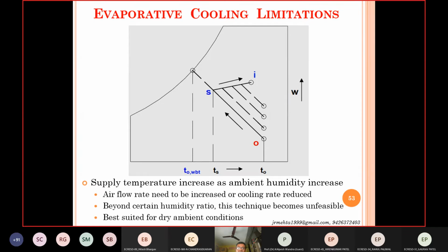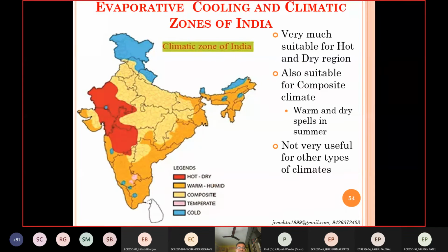But there is a limitation of evaporative cooling, as shown here: if your ambient is already at a higher humidity ratio, then you have to go on increasing the quantity of air that you handle, and still there is a limit to it. Otherwise it will create air drafts, which are already very high in desert coolers. Because in India there is a large portion which remains hot and dry for many months, evaporative cooling is a good choice even in the composite climates. For a couple of months at least, the ambient is such that you can go for evaporative cooling.